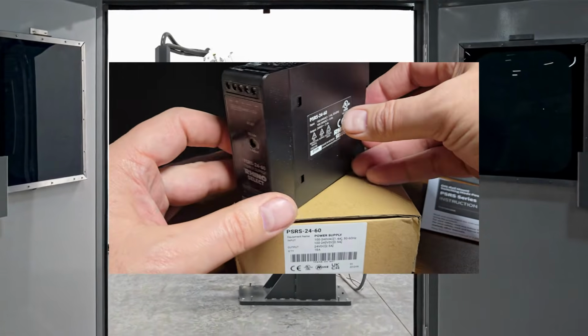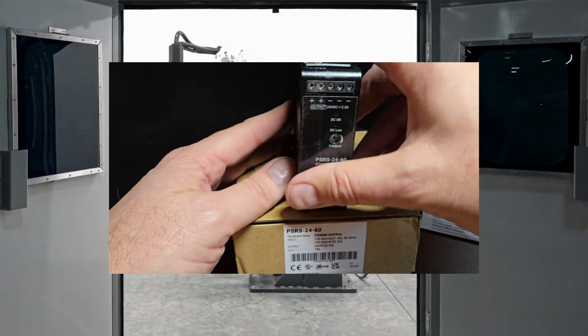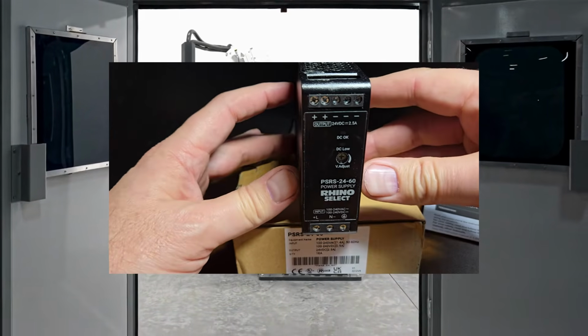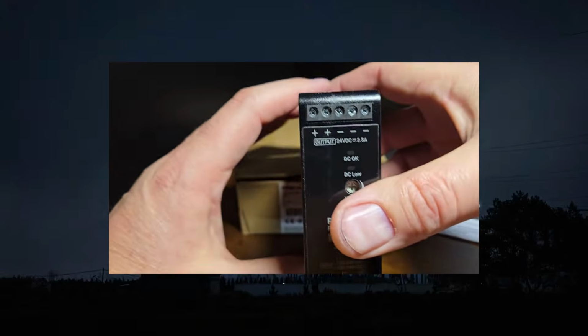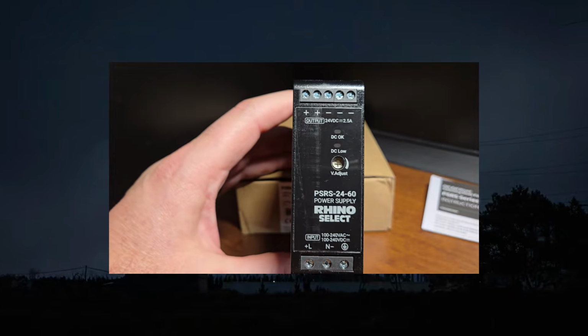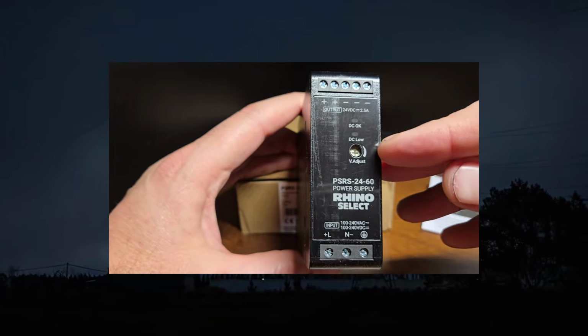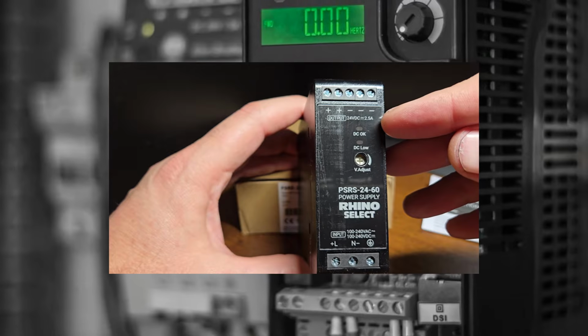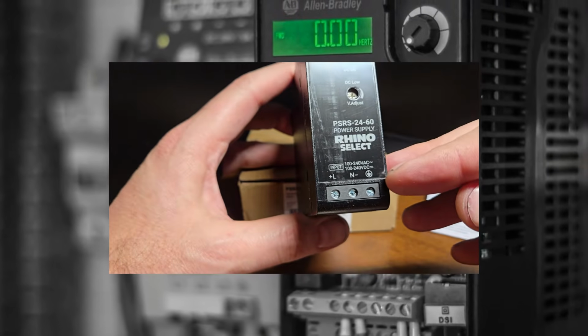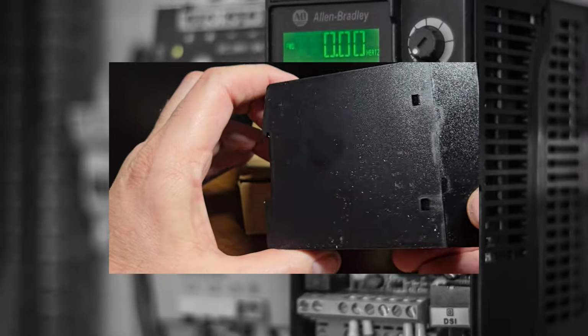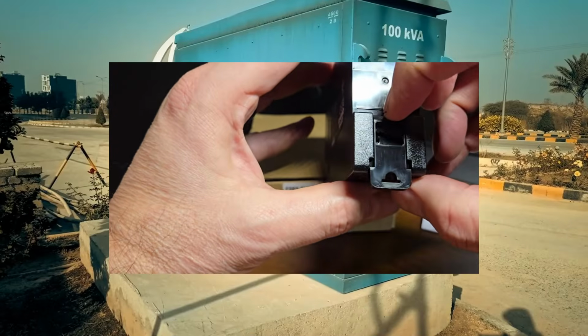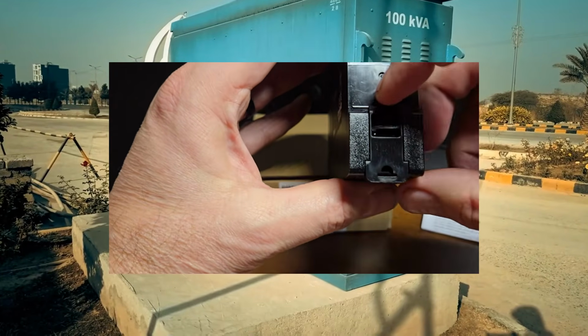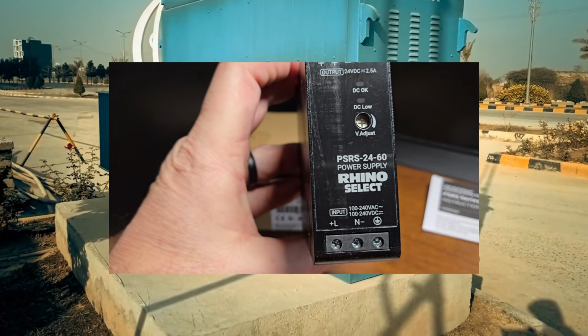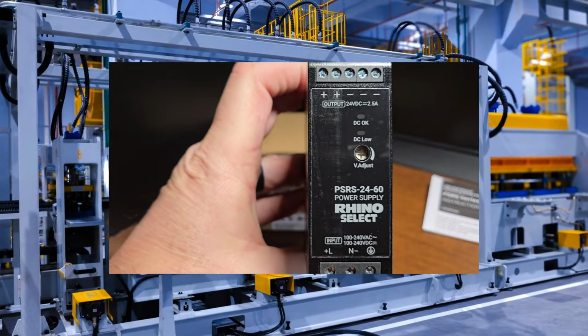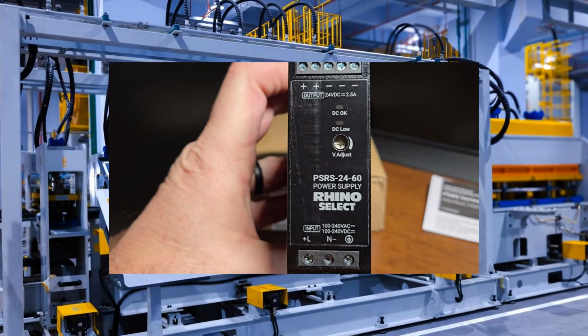The most vital function of an industrial power supply, like the PSRS 2460, is providing galvanic isolation. Imagine a massive voltage spike occurring on the incoming AC mains line due to a nearby motor starting or a lightning strike. Without isolation, that spike could travel directly through to the DC side, instantly destroying sensitive and expensive control components. Galvanic isolation physically separates the input, AC high voltage circuit from the output, DC low voltage circuit using a transformer. There is no direct metallic conductive path between the high side and the low side. Energy is transferred via magnetic fields.